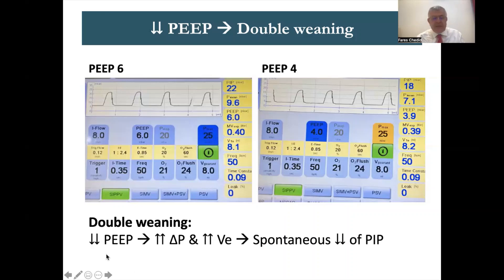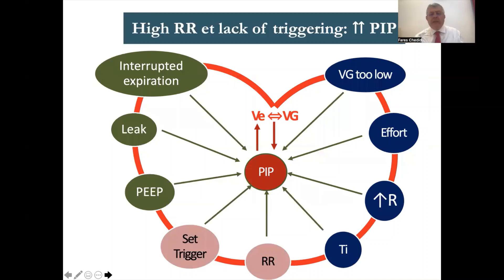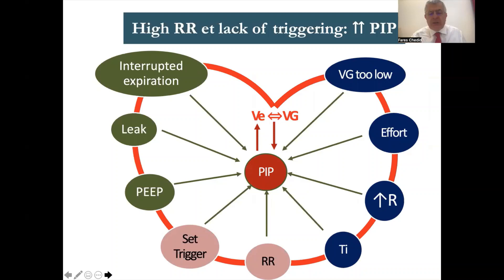To summarize dual weaning: decreasing PEEP increases the delta P, which increases expired volume, which causes the machine to spontaneously wean the PIP downward until VE returns equal to VG. Now I'll discuss set trigger and respiratory rate, because both work in the same way — if you don't allow the patient to trigger, or you set the rate too high, you will see a higher PIP.